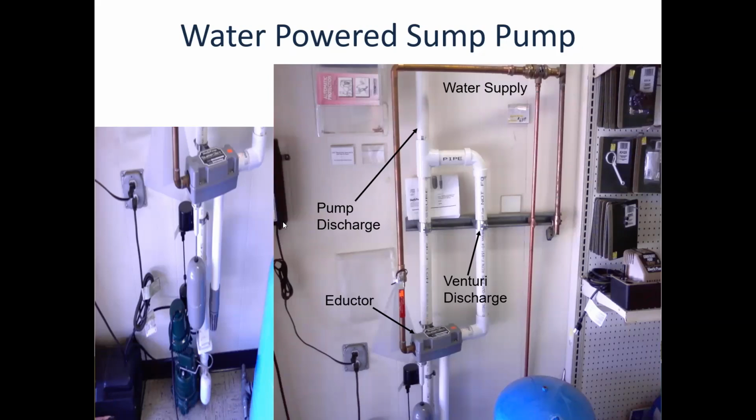Because it has that potential interaction between the pump's discharge and your potable water supply, you want to have a backflow preventer on this, so that whatever is in that sump isn't accidentally put back into your potable water. Most of the time, a sump like this is going to be considered a high hazard risk, just because we don't have control over what might be draining to or collecting in that sump.